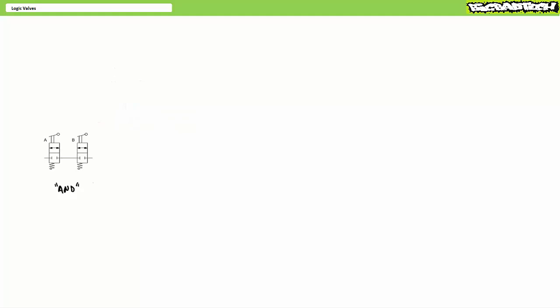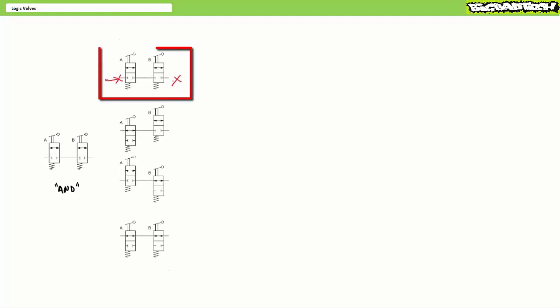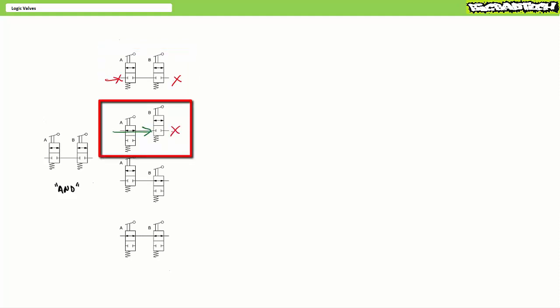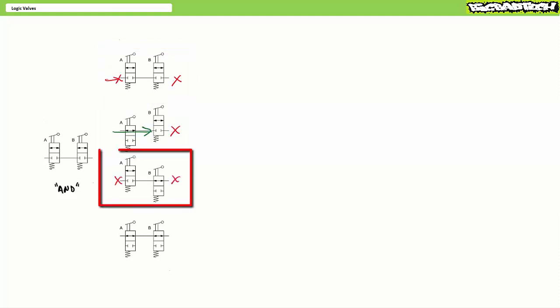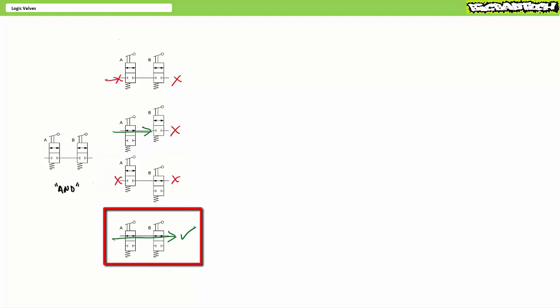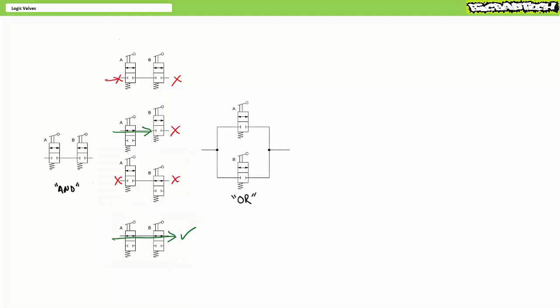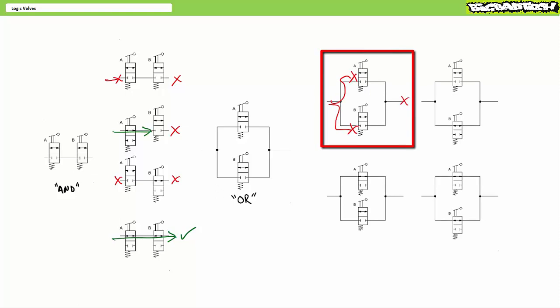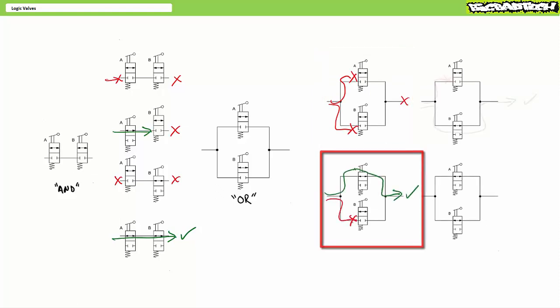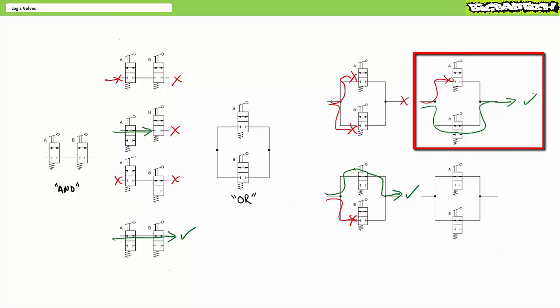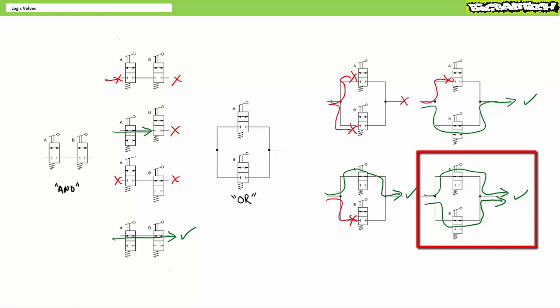There are alternative methods to implementing logical decision-making functions in pneumatic systems, but they aren't nearly as clean or easy to implement as logic valves. For example, one could rig up an AND function using a series connection of two normally closed valves — output only occurs when both valves are open. Similarly, an OR function can be implemented using a parallel connection of two normally closed valves — output occurs when either or both valves are open. These systems do exhibit logical AND and OR behavior, however they're messy.